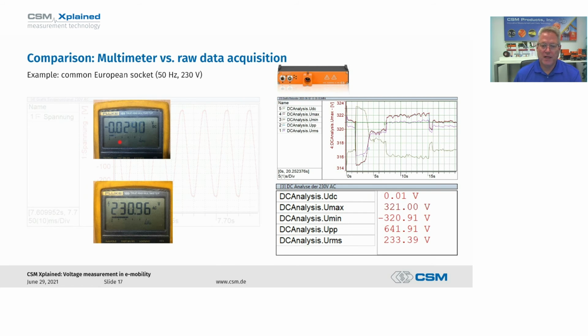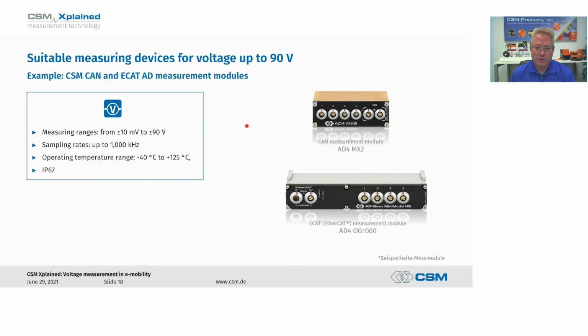Again, a voltmeter could come in and do similar measurements, but you're only going to get the true RMS value, which is our bottom one, and your DC voltage offset if there is any - here it's only 0.024 volts, very minor. Having two different measuring devices at two different times gives you a bit of a different result, but that's okay, they're very negligible. But you don't get your min, you don't get your peak to peak, and you don't get your actual max out of that.